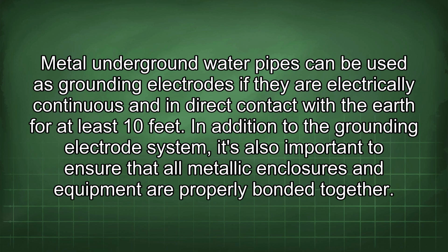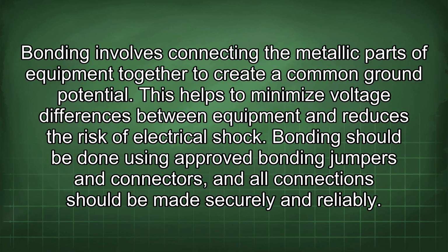In addition to the grounding electrode system, it's also important to ensure that all metallic enclosures and equipment are properly bonded together. Bonding involves connecting the metallic parts of equipment together to create a common ground potential. This helps to minimize voltage differences between equipment and reduces the risk of electrical shock. Bonding should be done using approved bonding jumpers and connectors, and all connections should be made securely and reliably.